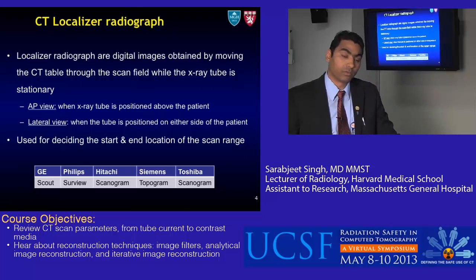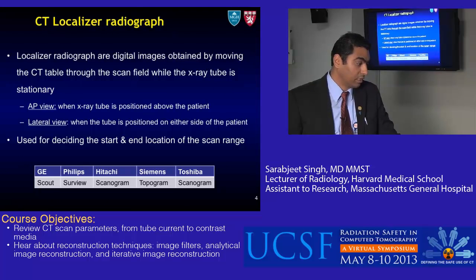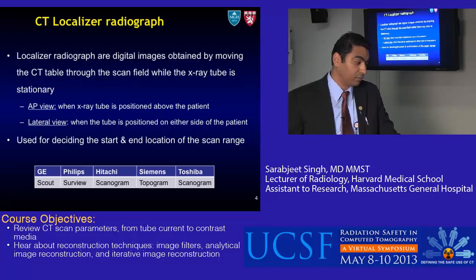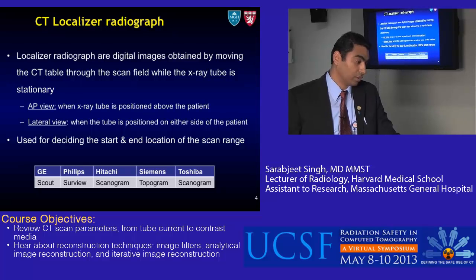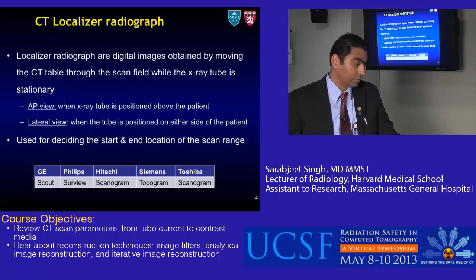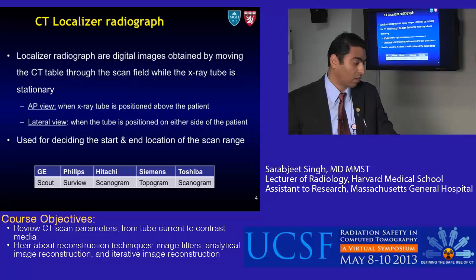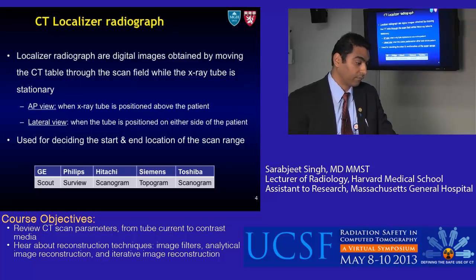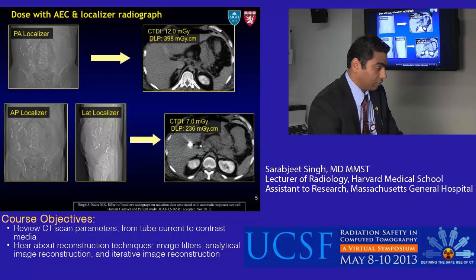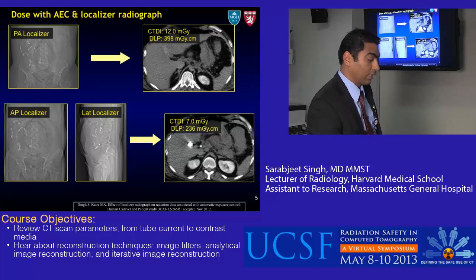Let's start with the CT localizer radiograph. This is a digital image obtained by moving the CT table through the scan field while the x-ray tube is stationary. We have an AP (anterior-posterior) view when the x-ray tube is positioned above the patient, and a lateral view where the tube is positioned on either side of the patient. This localizer is used for deciding the start and end location of the scan range. Different vendors call it by different names: Scout from GE, Surview from Philips, scanogram from Hitachi, topogram from Siemens, and scanogram from Toshiba. Here are examples of a PA localizer, an AP localizer, and a lateral localizer.